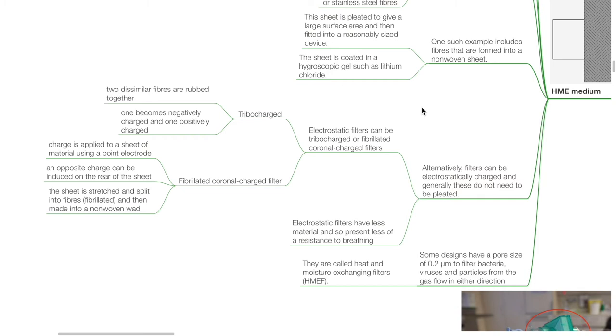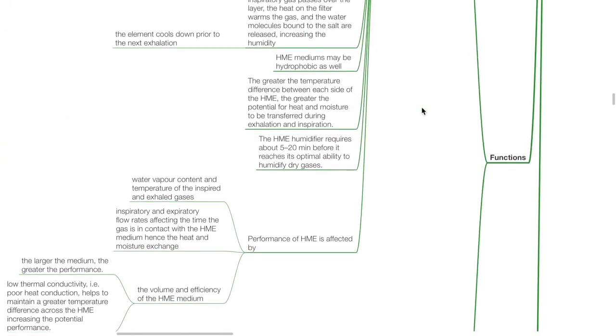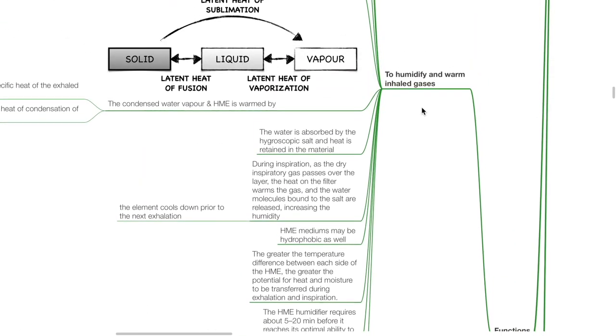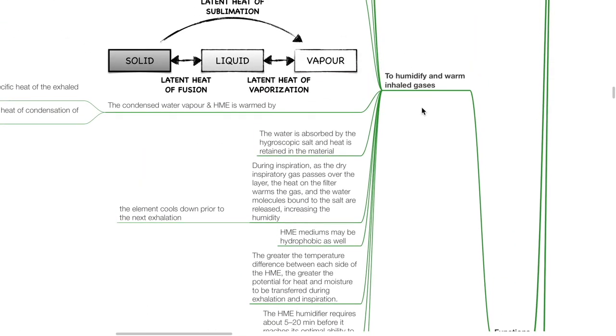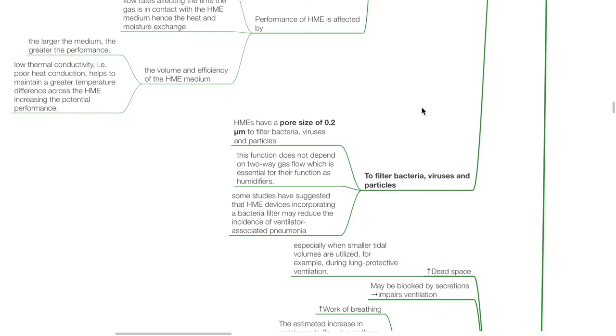Some HME designs have a pore size of 0.2 micrometers to filter bacteria, viruses and particles from the gas flow in either direction; these are called heat and moisture exchanging filters. Functions of the HME include humidifying and warming inhaled gases, and filtering bacteria, viruses and particles.